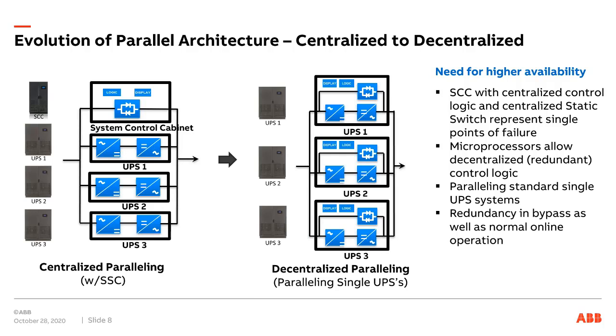of the UPSs, like if UPS 2 is having a really bad day, doesn't matter what it is, UPS 1 or UPS 3 can just take over and control the operation of the remaining part of the system. So in the name of high availability, the decentralized paralleling was invented. Obviously, it also makes it a little easier manufacturing-wise. Now you don't have to make a special UPS that's just a rectifier and inverter, and you do not have to manufacture system control cabinets.